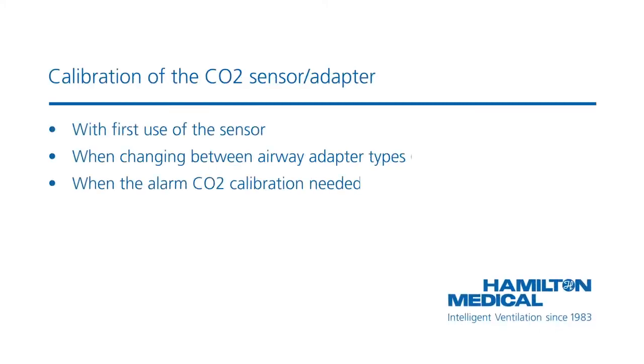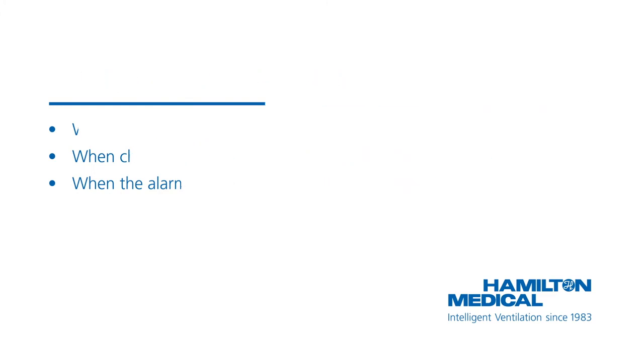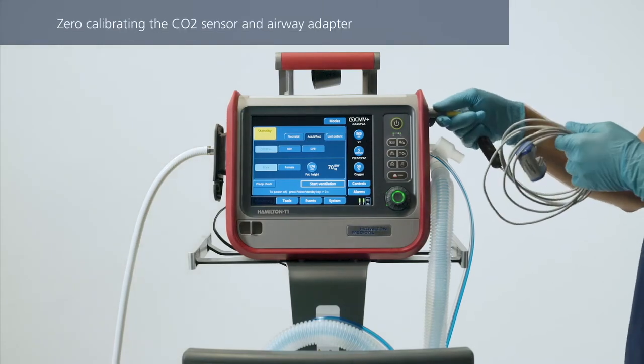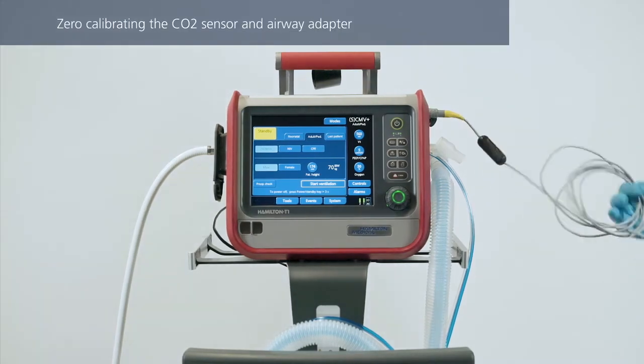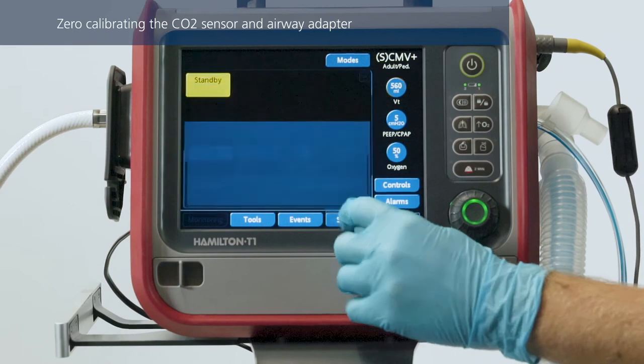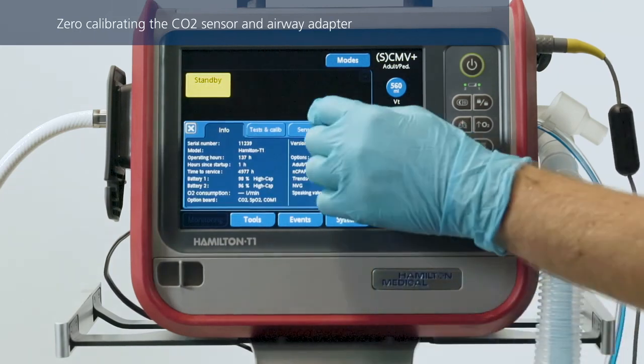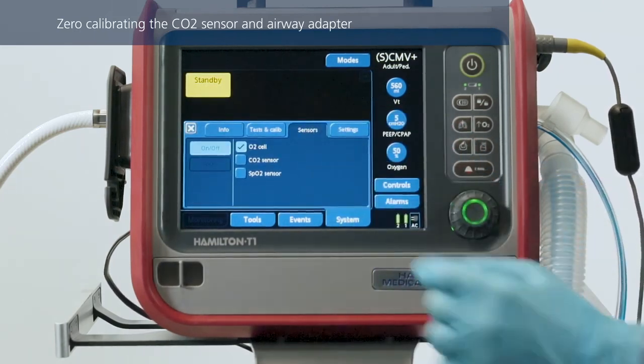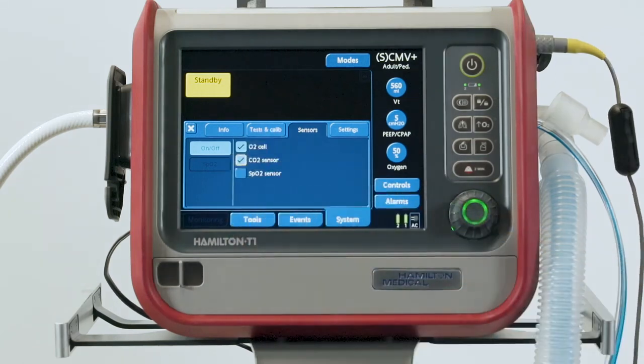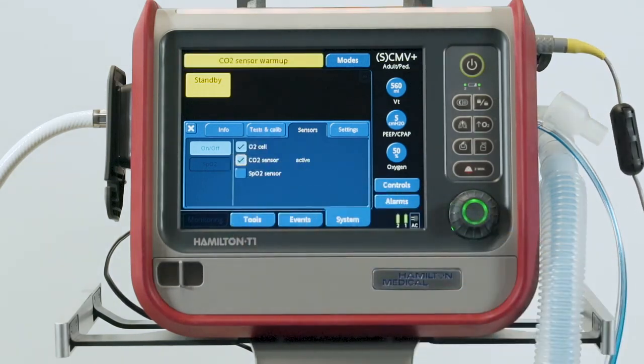The CO2 sensors are already calibrated before the ventilator leaves our factory, so you only need to zero calibrate the airway adapters. Firstly, connect the sensor to the ventilator. Check whether CO2 monitoring is enabled. Then wait about 90 seconds for the device to warm up.